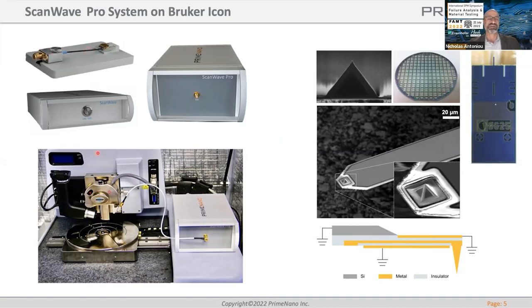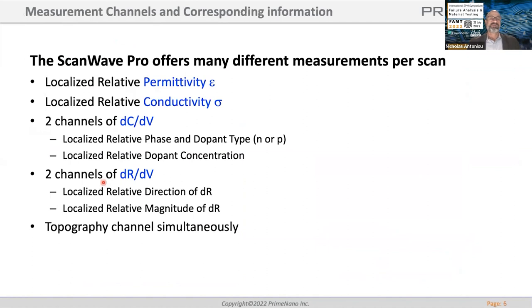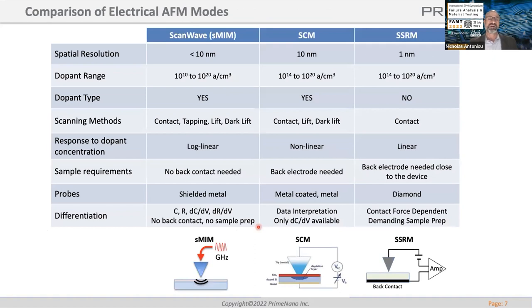This single probe is loaded onto the probe interface module and attached to an AFM system. What we actually measure is relative localized permittivity, conductivity, and with an AC signal we can do dCdV and dRdV. We still get the topography channel, so we get up to six channels of microwave information plus topography. These can be combined any way you'd like or seen individually.